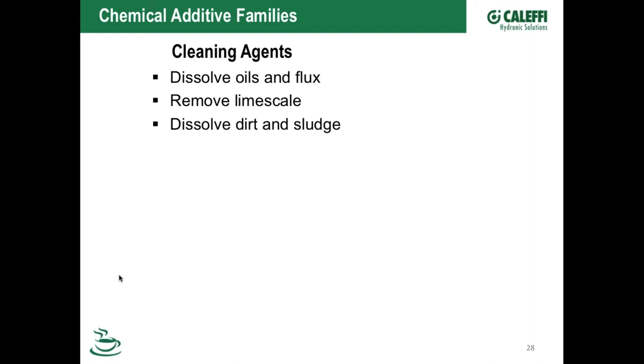So if you've got an older system where you're taking out an old boiler and notice a lot of limescale when you start taking the pipes apart, or break apart the old boiler and it's all scaled up, you might need a more aggressive cleaner, something like a vinegar and acid-based cleaner to dissolve those minerals. A typical soap-type cleaner isn't going to go after those hard, thick layers of mineral deposits that might have built up in there.